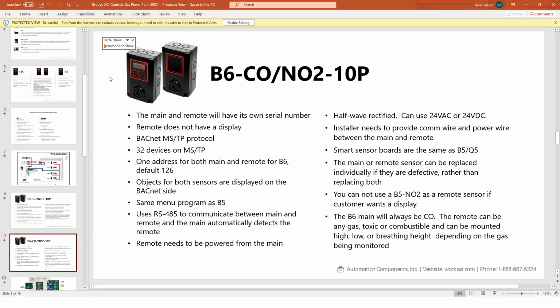So here's the BACnet version of it. Once again, the Q5 and the B6 are the same price - it's a BACnet MSTP protocol. The difference with the B6 is, using the same scenario with 8 sensors, instead of 16 addressable points, it'll just be 8 on the BACnet. That's kind of huge, because we tell customers the max is around 62 devices on a BACnet - usually. On MSTP, the RS-485 rules say 32.